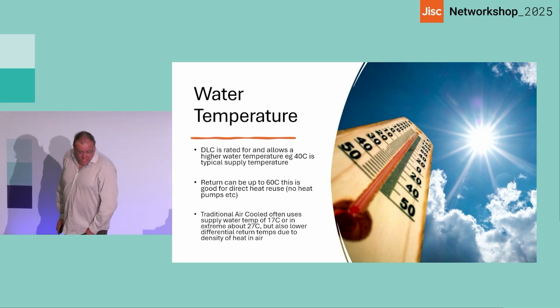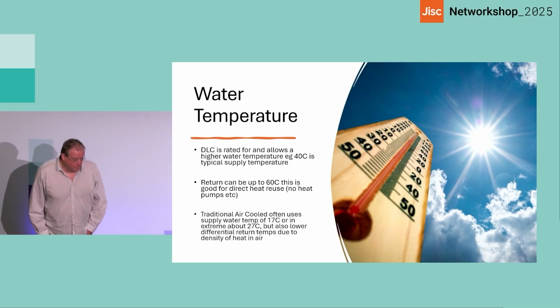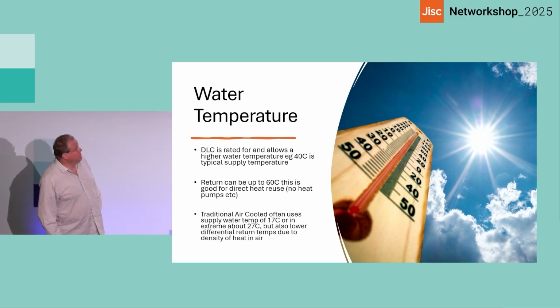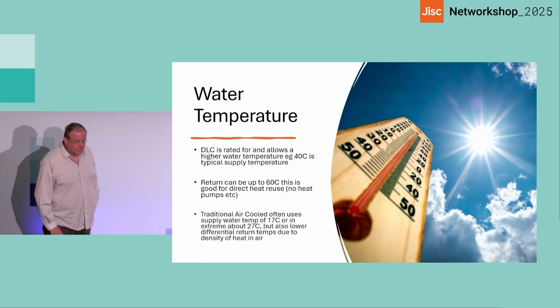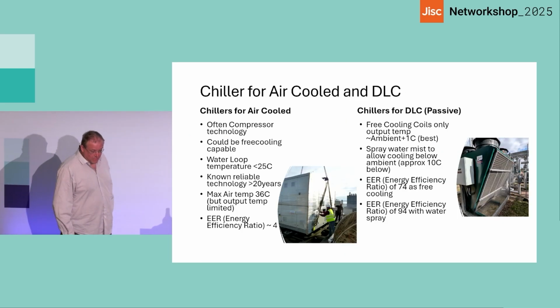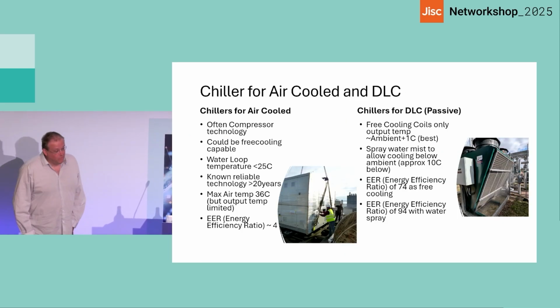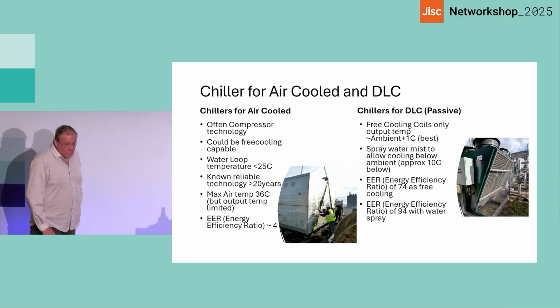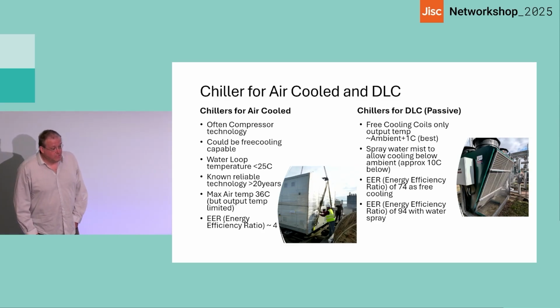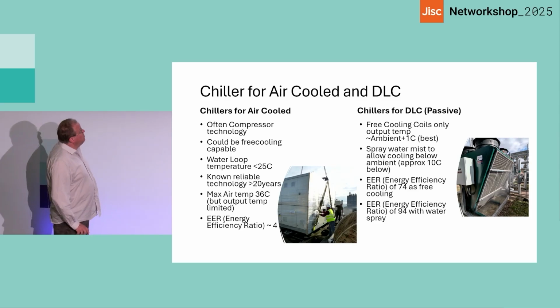So if you're trying to use lower supply temperatures, for air you can have a lot lower water temperature. You'll see there's some differences there. So basic system for chilled water. We often use it for air cooling and DLC now. Here's a picture of both.